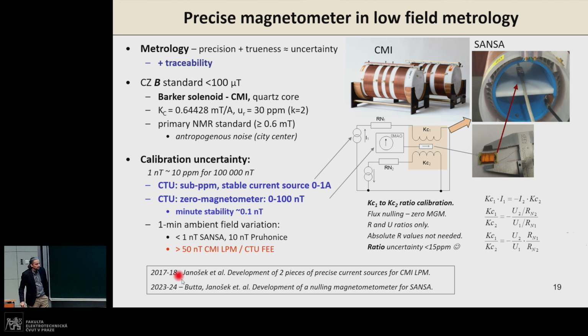So we are collaborating with the Czech Metrology Institute. We have provided them with very stable current sources. And we have also developed a very low noise nulling sensor with a very low range, where the only requirement for it is zero stability in a short time. So we can see here a cross calibration of 2 coils against each other, utilizing the zero sensor here. If we compensate the 2 fluxes of the 2 coils, and if we record the currents, we can establish the constant of the second coil to be calibrated.